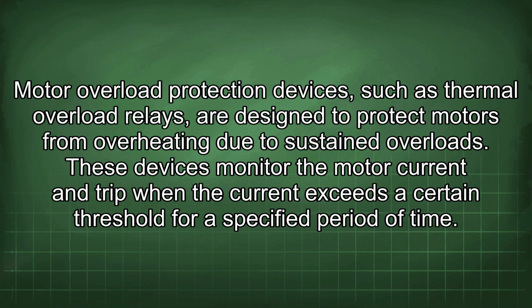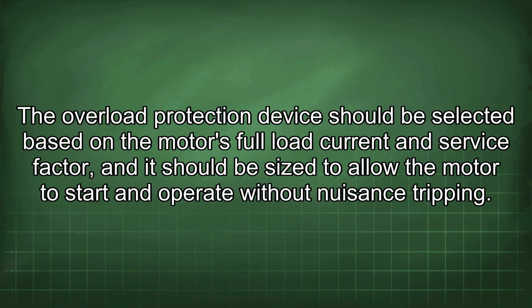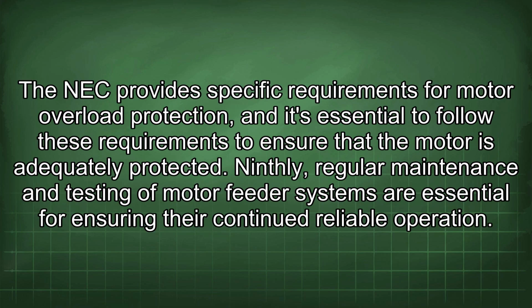Motor overload protection devices, such as thermal overload relays, are designed to protect motors from overheating due to sustained overloads. These devices monitor the motor current and trip when the current exceeds a certain threshold for a specified period of time. The overload protection device should be selected based on the motor's full load current and service factor, and it should be sized to allow the motor to start and operate without nuisance tripping.